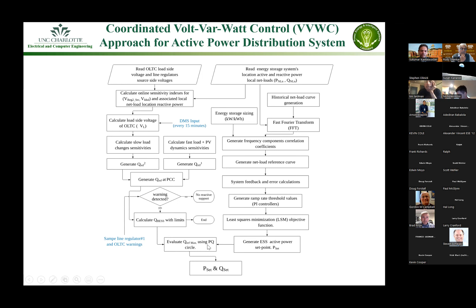From there, generate the QREF at the PCC and calculate the limits for the battery related to the inverter, as I mentioned previously, because it depends on reactive power and on the inverter. So calculate the limit, include the warning detected from the taps from operation of the regulators, and then from there, look at the reactive power capability, calculate from the real power, and set as a P set and Q set.